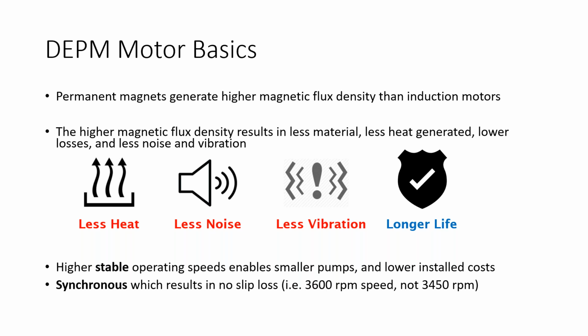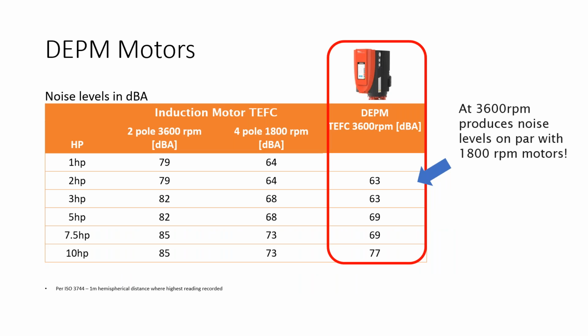So our general 3600 RPM or 1800 RPM motors don't really operate at that speed. They're usually at 3450 or 1760. These motors are actually running at 3600 RPM, which means you get the head and the power efficiency right off the bat. Now somebody said, oh geez, but Rich, those two-pole motors, they're so darn noisy.